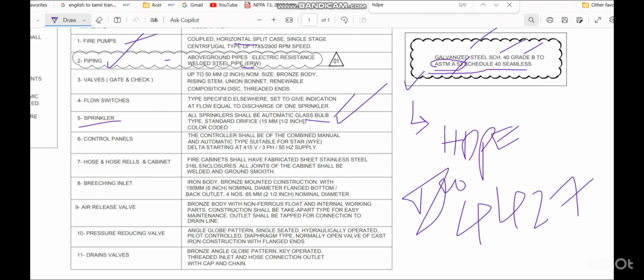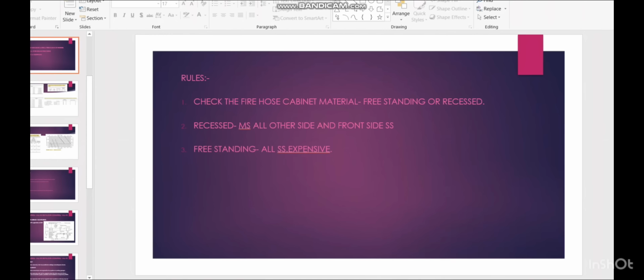And normally for the NFPA we can use both types, glass bulb and also fusible link. Both are allowed as per NFPA. And for the hose reel, the important thing we have to see is what type of material they have given. It's stainless steel 316L they have followed. Here we have two important things.